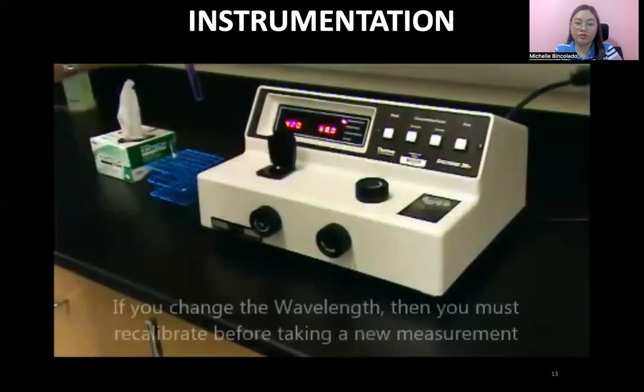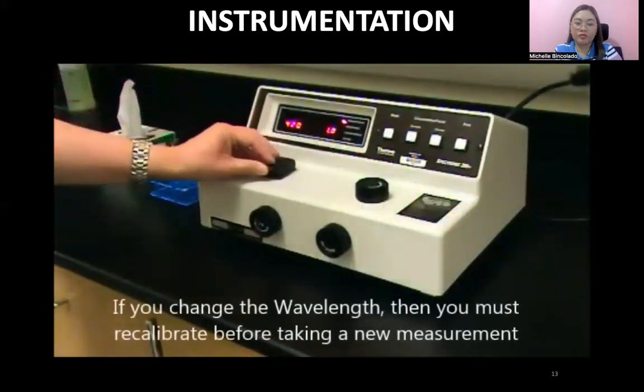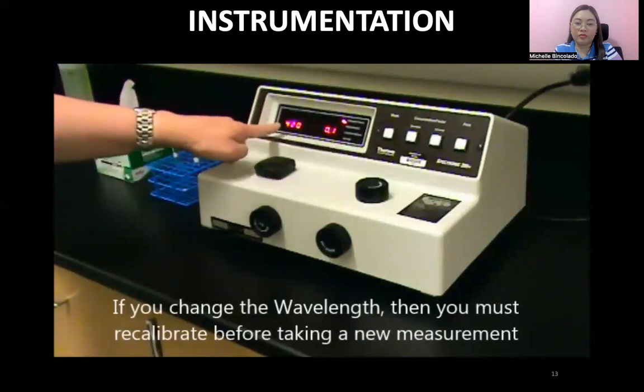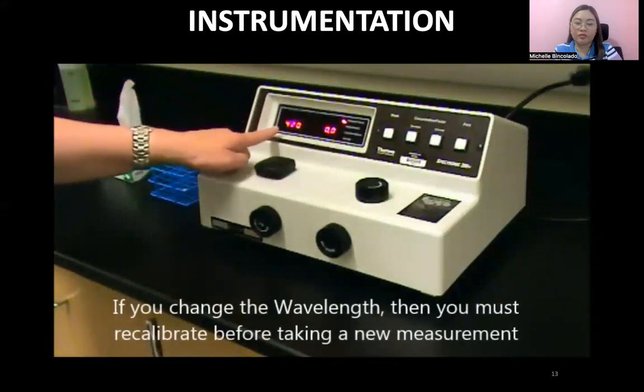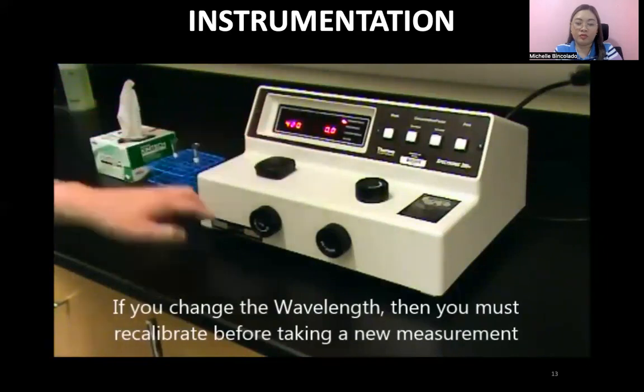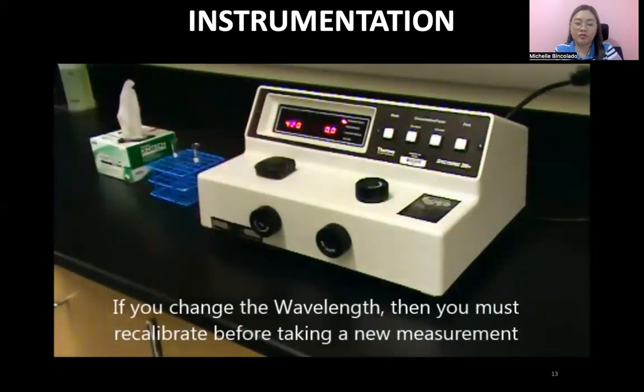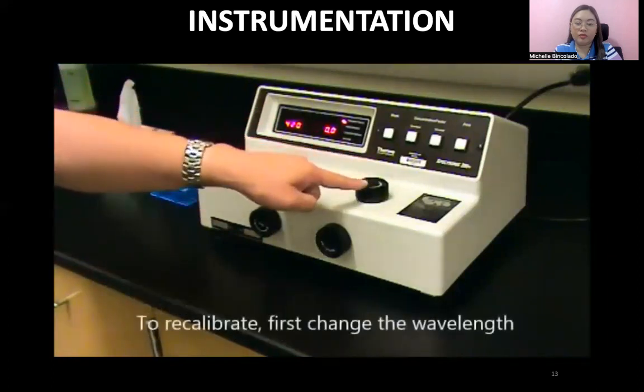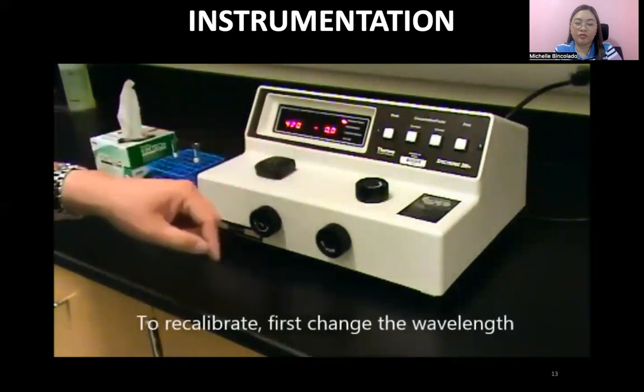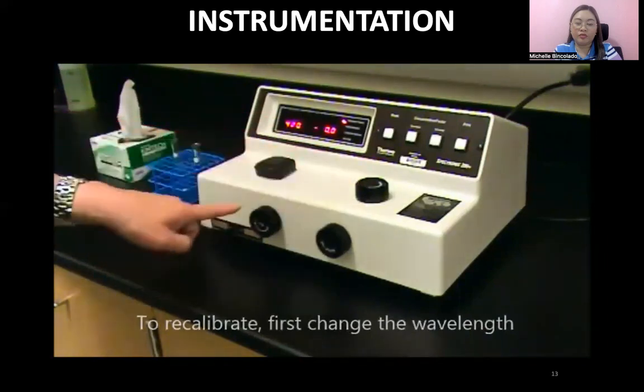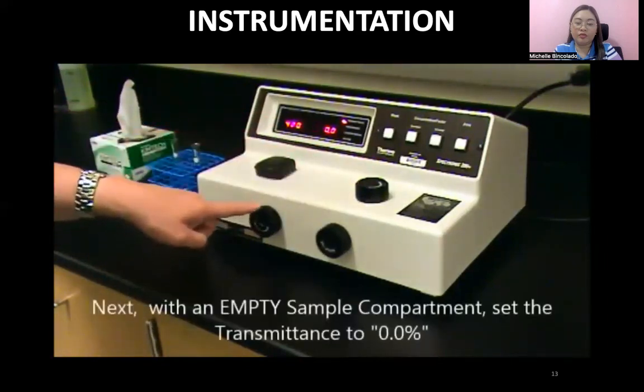But once you decide that you want to record at a different wavelength, let's say we want to switch from 420 to 480 nanometers, now we have to go through the entire calibration method one more time. So we'll have to begin by first changing the wavelength to the desired 480. We'll have to zero the machine using the 0 control knob on the left.